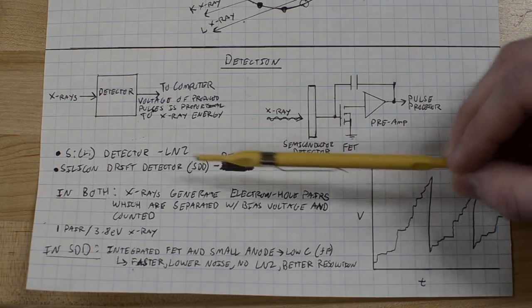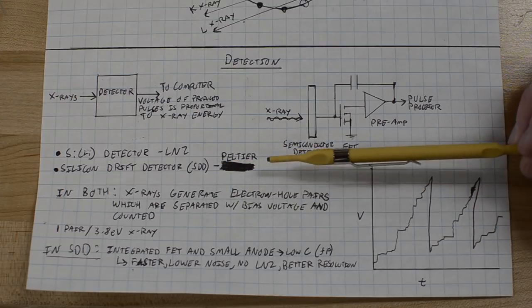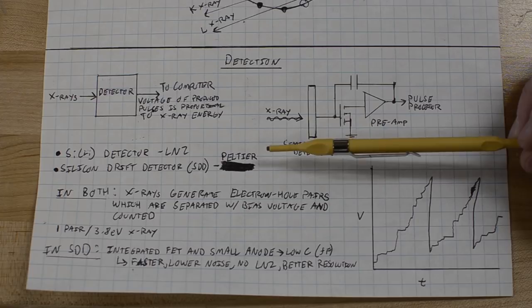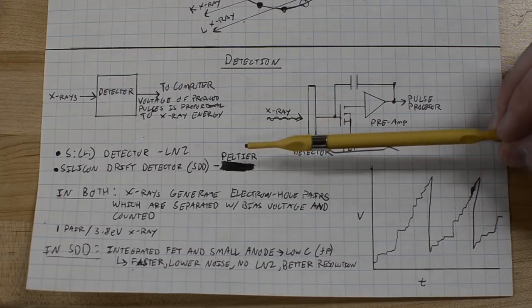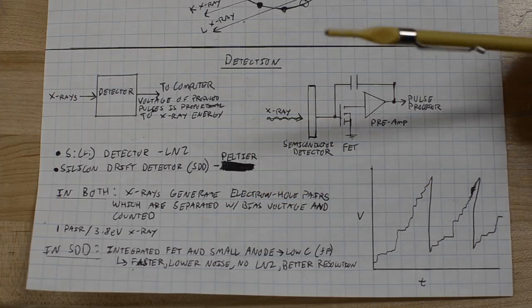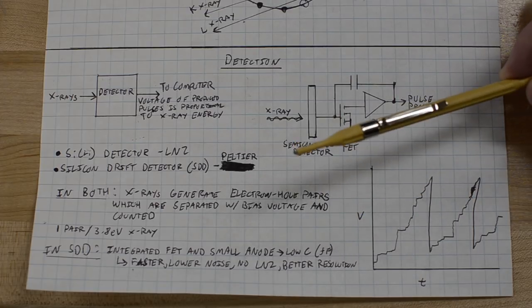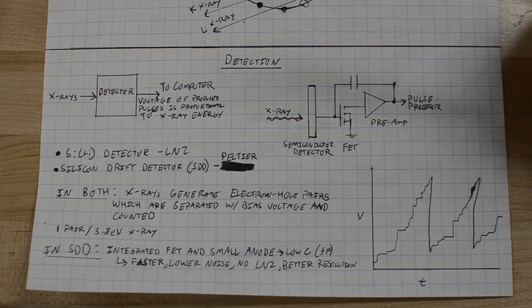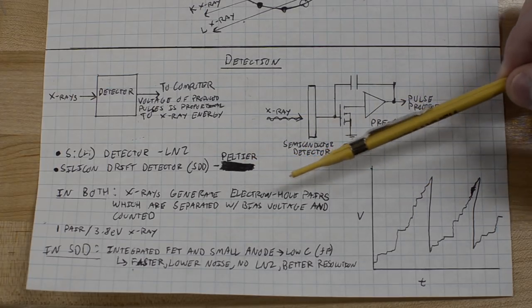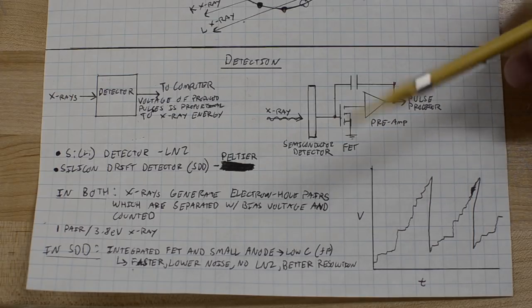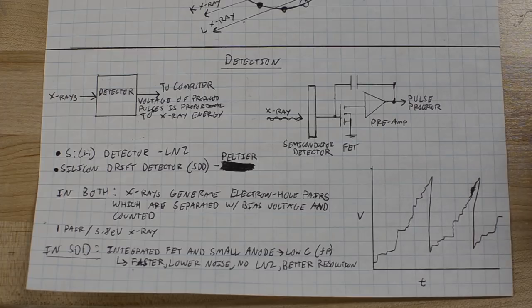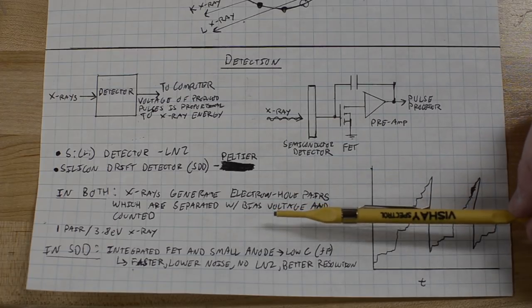I was lucky enough to pick up an SDD, or a silicon drift detector system, and these need only be cooled by a Peltier module, to get the electronics down so the thermal noise is low enough that you can actually get useful information out of it. This is a much easier system to deal with and a cleaner system as well. In both of these, you're probably already guessing at how they work. The X-rays will generate electron-hole pairs when they strike the semiconductor.